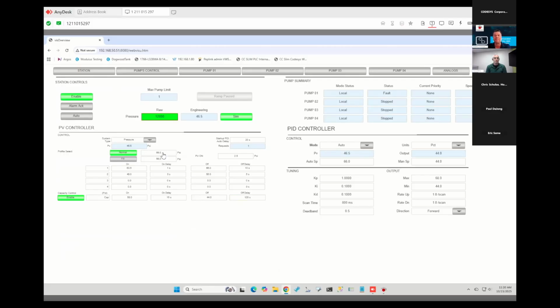So you've got a set point that you're trying to maintain. You've got all 4 pumps, your on and off set points for those, and then also your PID and all your tuning involved for that PID. This allows them to really tighten up how quickly and how closely it maintains the set point. In a water wastewater system, usually a couple PSI doesn't matter. But if you're getting into some where you're filling or pressurizing tanks, they need to be tighter on the tuning parameters. And from here now, I can test and make sure it's working properly.